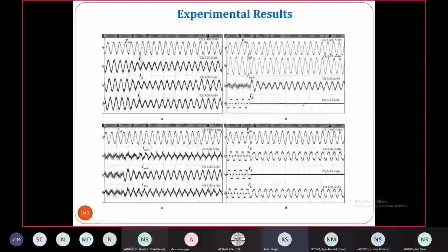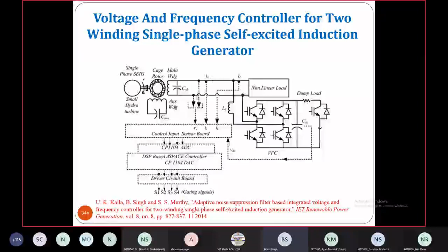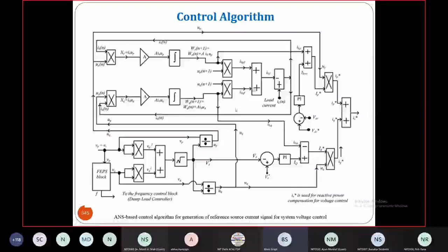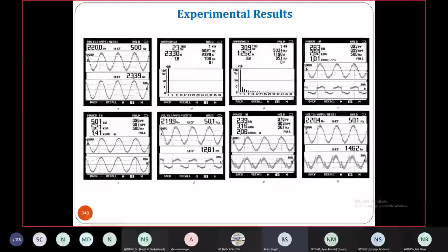We worked out the same for single phase also. One benefit here is that a 3.7 kilowatt machine is able to give 5.5 kilowatt output, meaning we can take a hydro turbine rated around 5.5 kilowatt. Because we are operating as a balanced two-phase machine corresponding to single phase operation, we maintain constant power output with constant power input. The load controller takes care of operating the machine at constant power while the load varies. This works well for canal type or run-of-river type systems, feeding non-linear and varying loads, with voltage and frequency regulated in all cases.